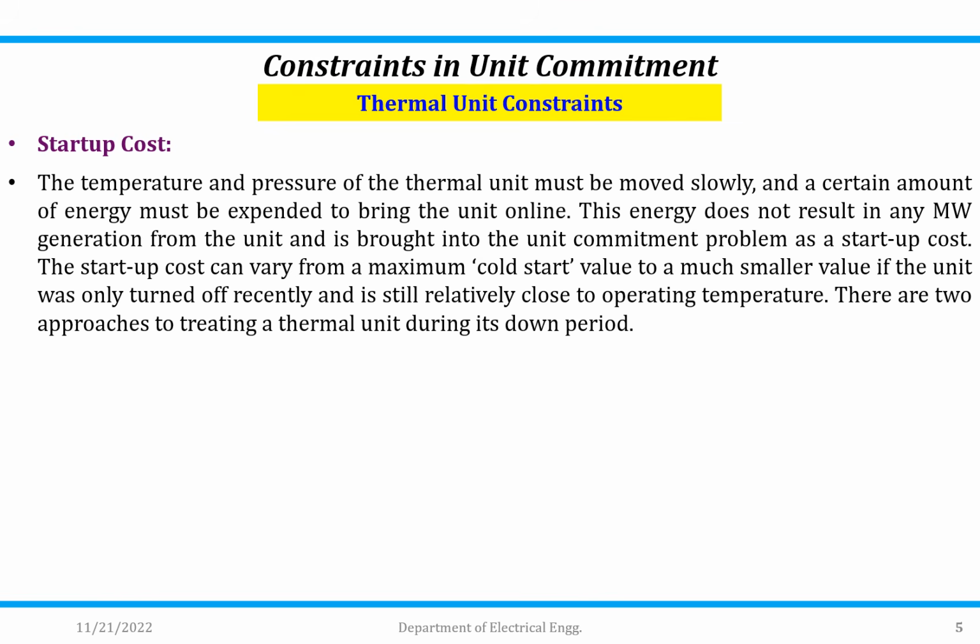Now the next one is the startup cost. The temperature and the pressure of the thermal unit must be moved slowly and a certain amount of energy must be expended to bring the unit online. This energy does not result in any megawatt generation from the unit and it is brought into the unit commitment problem as a startup cost.